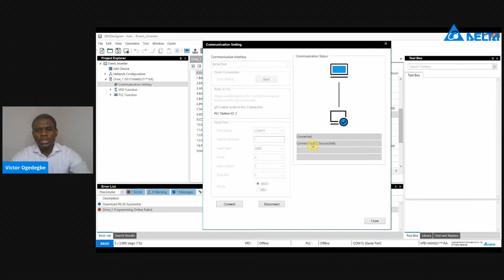You can choose to download both the parameters of the inverter and the PLC program of the internal PLC at the same time. Start downloading. You can see the download success, and you can see the progress of the downloading. With one cable, you have programmed and downloaded to the internal PLC and the parameter of the drive. So that is easy connection for upload and download.